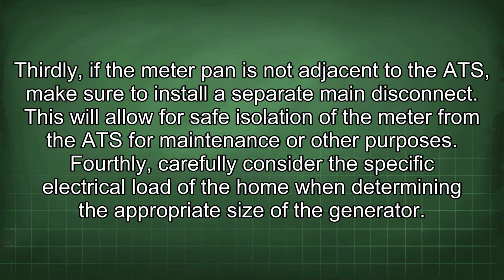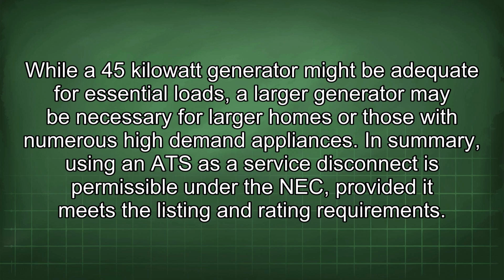Thirdly, if the meter pan is not adjacent to the ATS, make sure to install a separate main disconnect. This will allow for safe isolation of the meter from the ATS for maintenance or other purposes. Fourthly, carefully consider the specific electrical load of the home when determining the appropriate size of the generator. While a 45 kilowatt generator might be adequate for essential loads, a larger generator may be necessary for larger homes or those with numerous high-demand appliances.